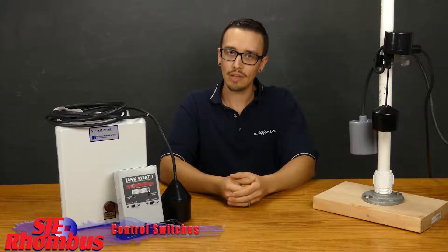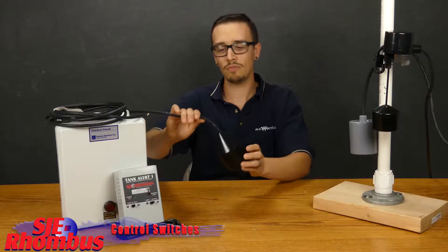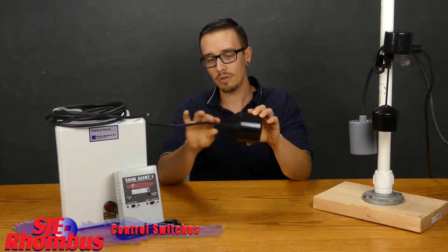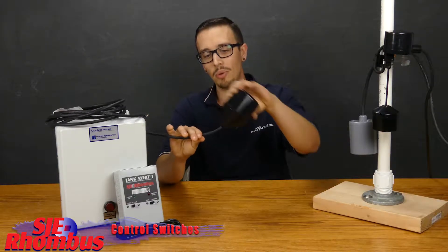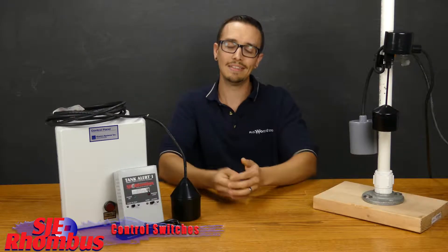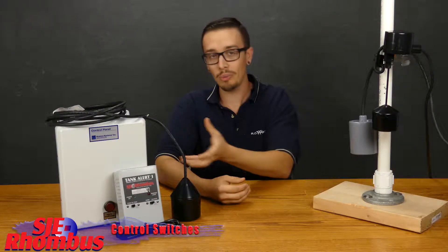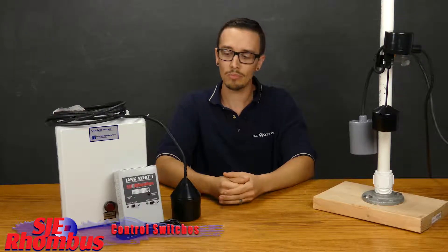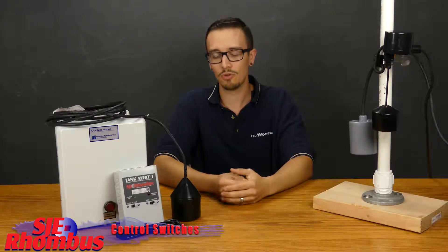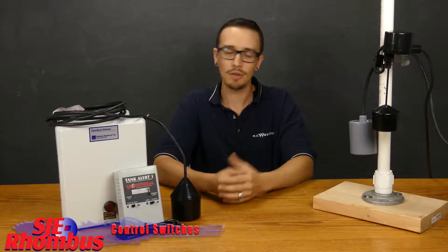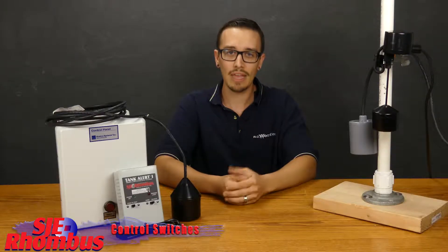Now the thing with control switches is they are typically narrow angle once again. So if you watch the previous video, you saw they only require typically a relatively short tether, but control switches are intended only for use with control panels. They aren't able to take the amperage. Generally speaking, the control switches that SJE Rhombus offers are rated for 5 amps.